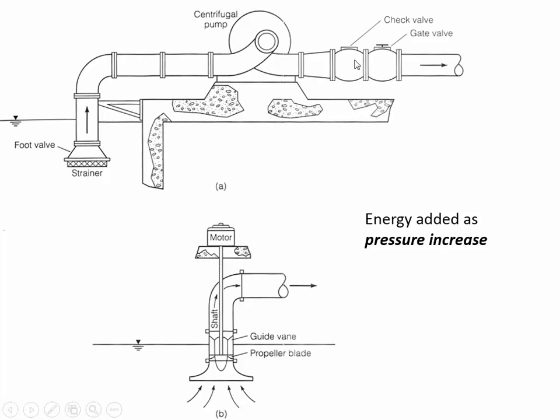And so it's just easier to have a check valve so that the water can only go towards the right, or the water can only go out of the pump and not back towards the water. And if this pump isn't able to self-prime, then you have to have a valve down here and close it, and then take a hose and try and fill up the suction side and fill up the pump, and then you can turn it on. So those kinds of pumps are a little bit hard to deal with.